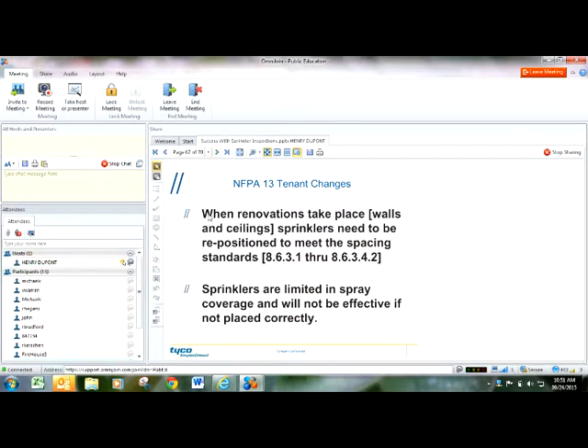If you're doing an inspection on a building that's gone through some recent renovations, you need to check the sprinkler head spacing. It's very common for people to neglect, and not even know, that if they move their walls around, their sprinkler heads are likely going to need to be moved as well. So if you go into a building where you're doing any kind of inspection, say an inspection to approve the above ceiling electrical before they get their C of O, you need to be asking them, hey, did you take into consideration your sprinkler head spacing?